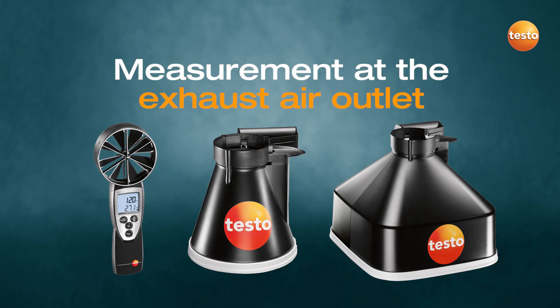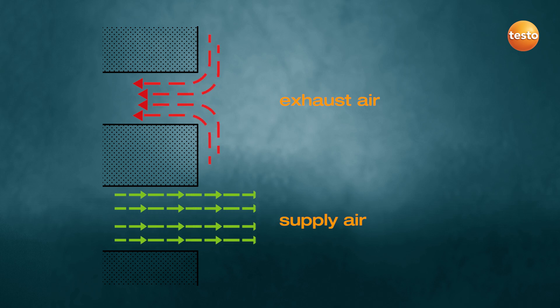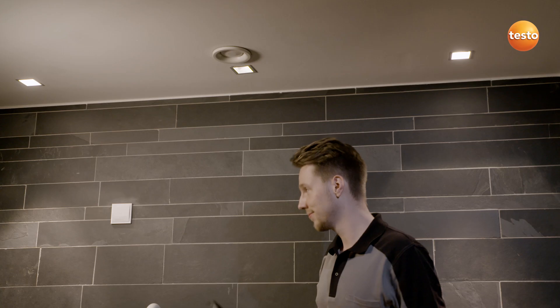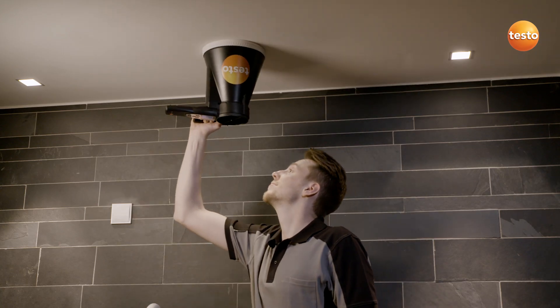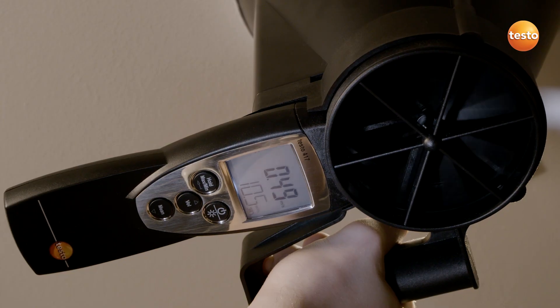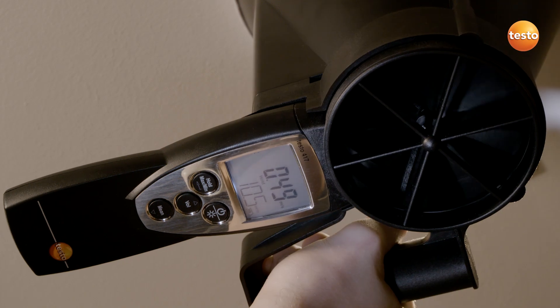This is how you measure properly at the exhaust air outlet. A funnel is required to measure the exhaust air. The reason? There is no directed flow profile available for exhaust air as the air is sucked in funnel-like from the room. This means there is no definable area in the room via which the volume flow can be determined. This challenge is easily solved with the Testo 417 funnel, because the funnel creates defined flow conditions at some distance from the plate outlet in a fixed cross-section.